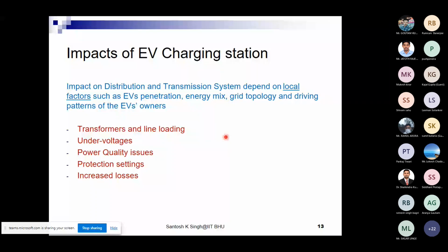On top of that, the transformers in use are low frequency transformers, designed with insulation strength and isolation capability meant to last 50 years. Now we are introducing higher order harmonics, so we have to think about the life and aging of those transformers. Most of the time, core loss calculations—eddy current and hysteresis losses—are based on standard 50 Hz conditions, but now we have to calculate them for higher frequencies, which means additional losses or heat in those transformers. That is a very serious concern.